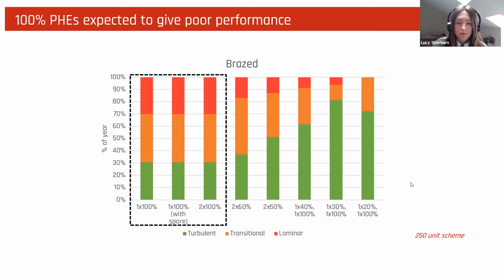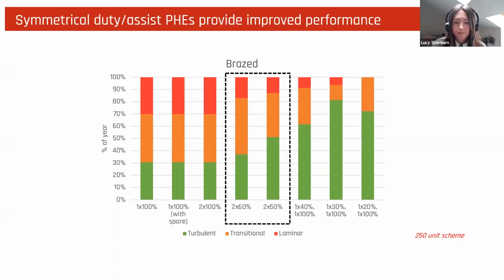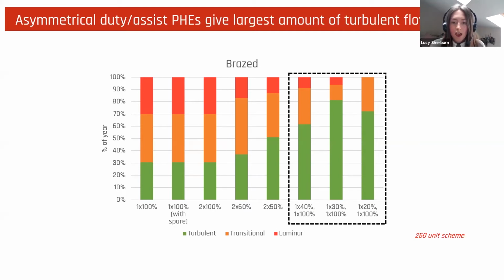We can see that duty plates and plates sized at 100% give the least amount of turbulent flow and the largest amount of laminar flow, so they should probably be avoided going forward. Next slide, please. The symmetrical duty assist plate heat exchangers provided an improved performance. With the 2 plates sized at 60% or 2 plates sized at 50%, the laminar flow amount decreased and the amount of turbulent flow increased as well. And next slide, please. We see that the asymmetrical duty assist plate heat exchangers, those that have the jockey plate, provided the highest amount of turbulent flow and really limited the amounts of laminar flow.